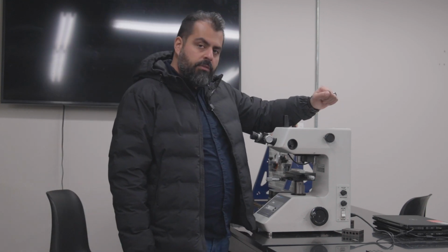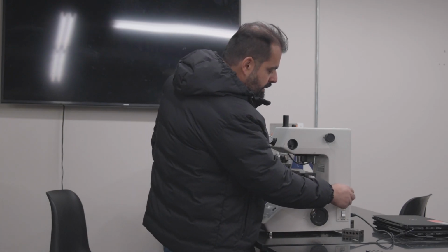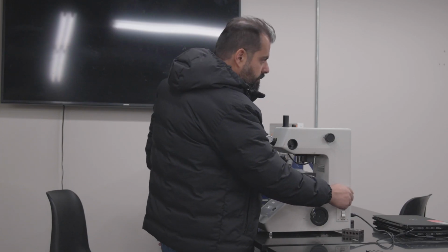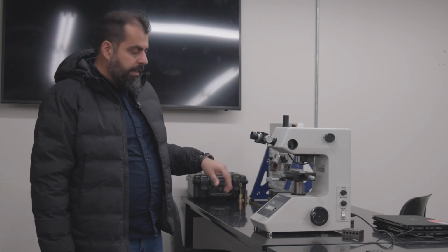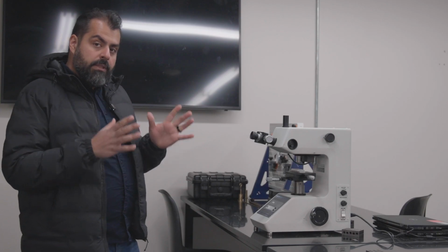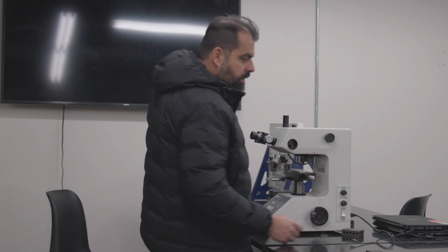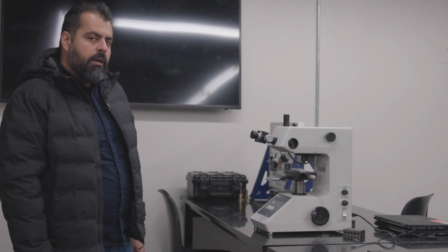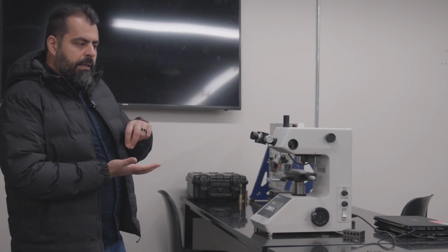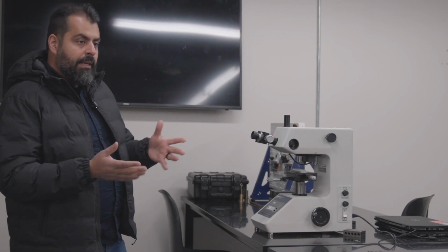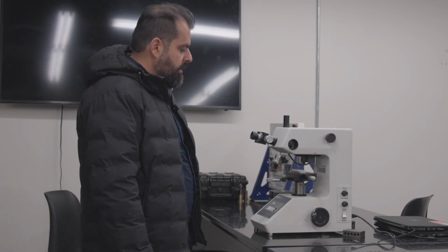That's how with this knob you can actually set the force that you're applying. And with this knob you can change the light. The lighting is the most important part of the analysis because we are going to see later on that using the lights we can actually see the indent, and we can change the load time. That wouldn't really change the hardness value, but if you make sure your load indentation is applied over like 20 seconds, you are going to have a better indent, and it's going to be easier for you to make the measurements. Of course, there's another button here.